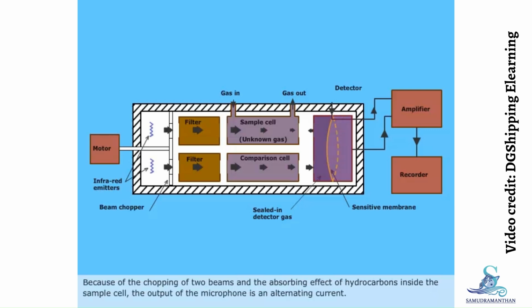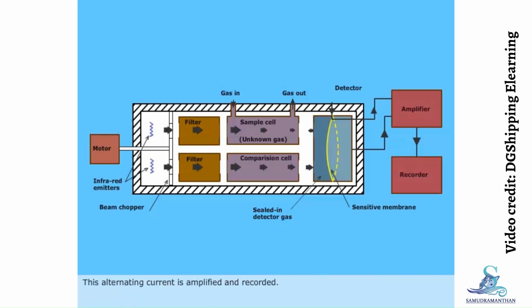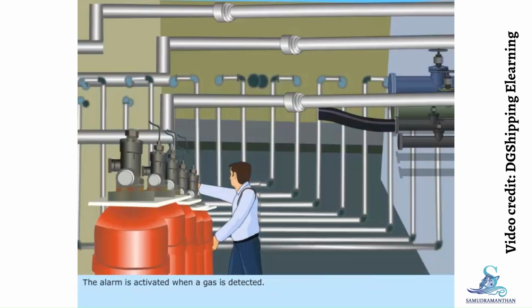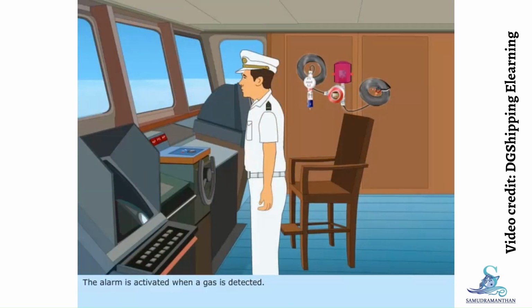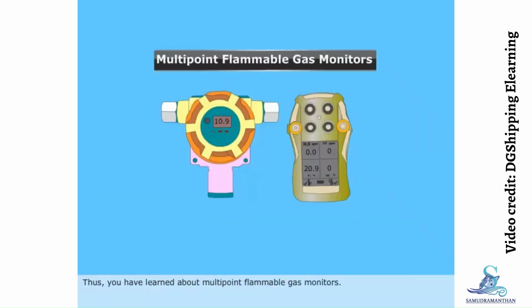Because of the chopping of two beams and the absorbing effect of hydrocarbons inside the sample cell, the output of the microphone is an alternating current. This alternating current is amplified and recorded. The alarm is activated when a gas is detected. Thus, you have learned about multi-point flammable gas monitors.